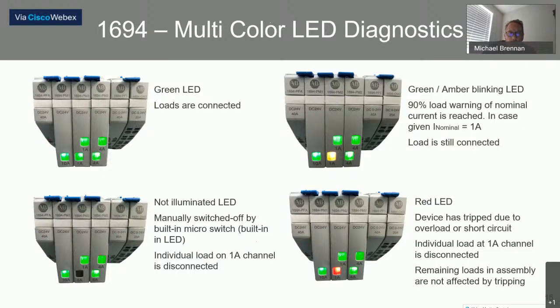When you look at each of the loads, if the loads are connected and turned on, then you'll see a green light. When you've reached 90% of the load capability of the output, and you'll see each one of the outputs is labeled based on current, you'll start to get a flashing green amber LED. One of the things we've talked with customers about that they've struggled with, if they have multiple power supplies in a specific application, is how do they know which power supplies are loaded? What are they loaded to? In this case, you can visually look at when you've reached 90% of load on a specific individual output.